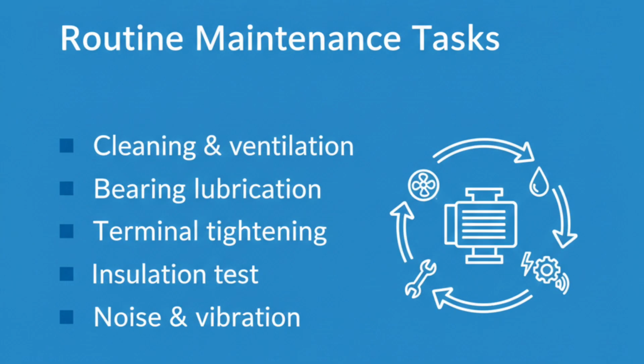Routine maintenance involves several simple but critical checks. Cleaning is necessary to prevent dust from blocking cooling air passages. Bearings must be lubricated at specified intervals to avoid overheating and seizure. Terminal connections should be tightened because loose joints cause sparking and excessive heating. Insulation condition should be tested periodically using an insulation resistance tester, especially in humid environments or marine ships. Operators should always listen for abnormal noise and feel for vibration during running.